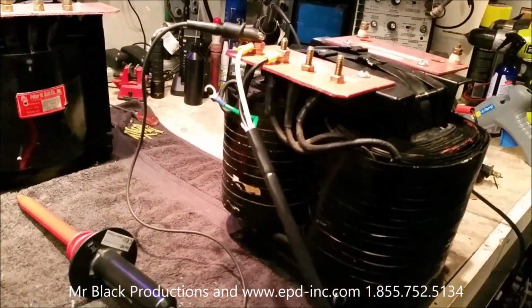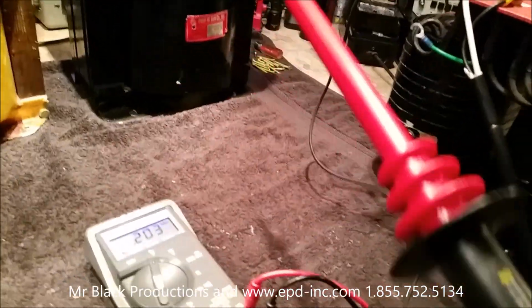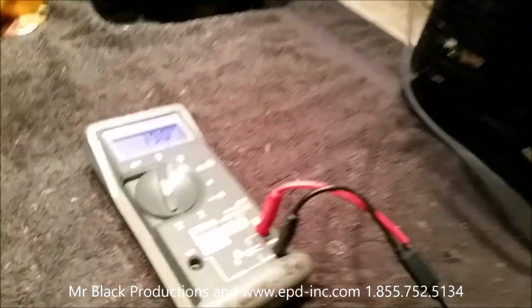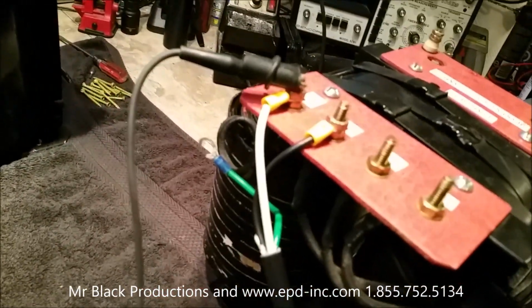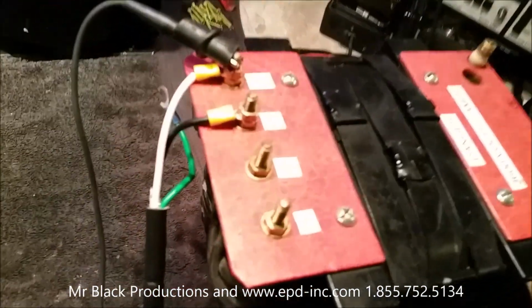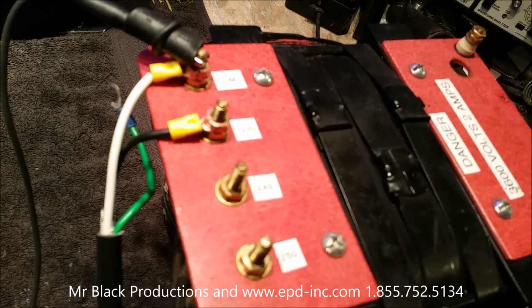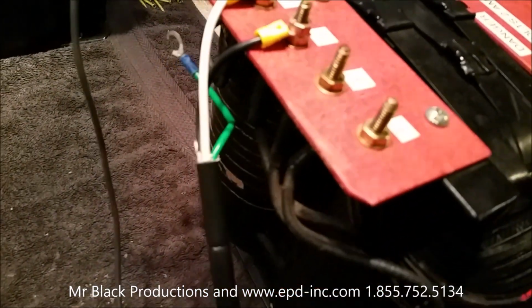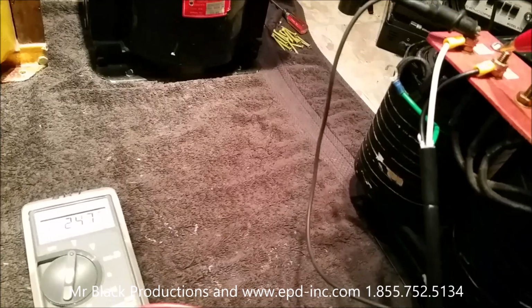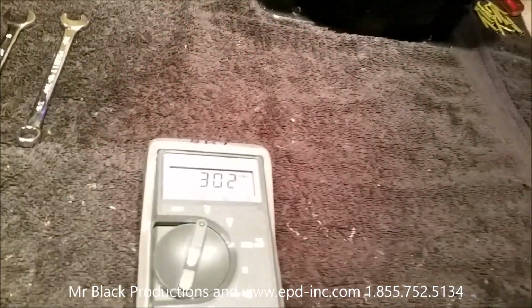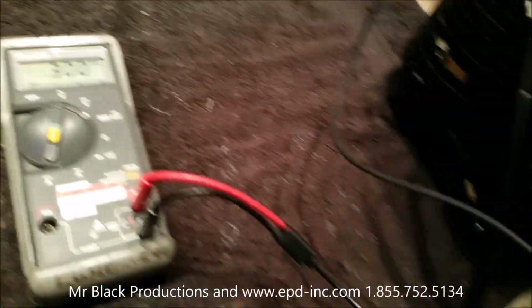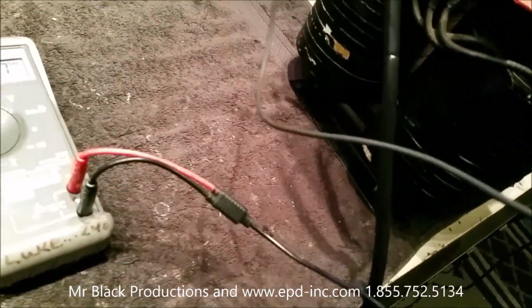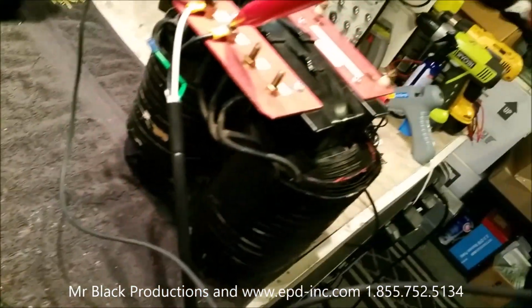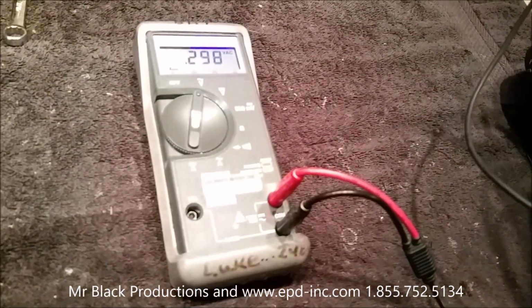This transformer's in a state of flux. Now we're going to use a reduction probe. We've got this set on AC setting, and we're going to look at our common, which is common 230, 240, 250. We're going to probe that. Now, because the transformer's in a state of flux, or working, there's a little bit of ambient eddy currents coming off the transformer, and it's getting into my probe.